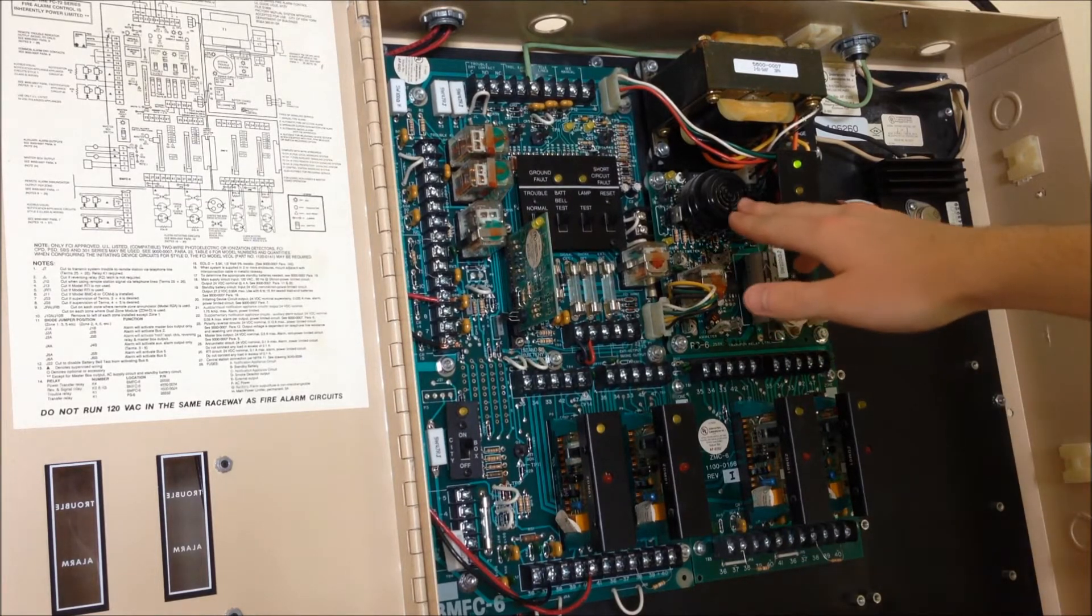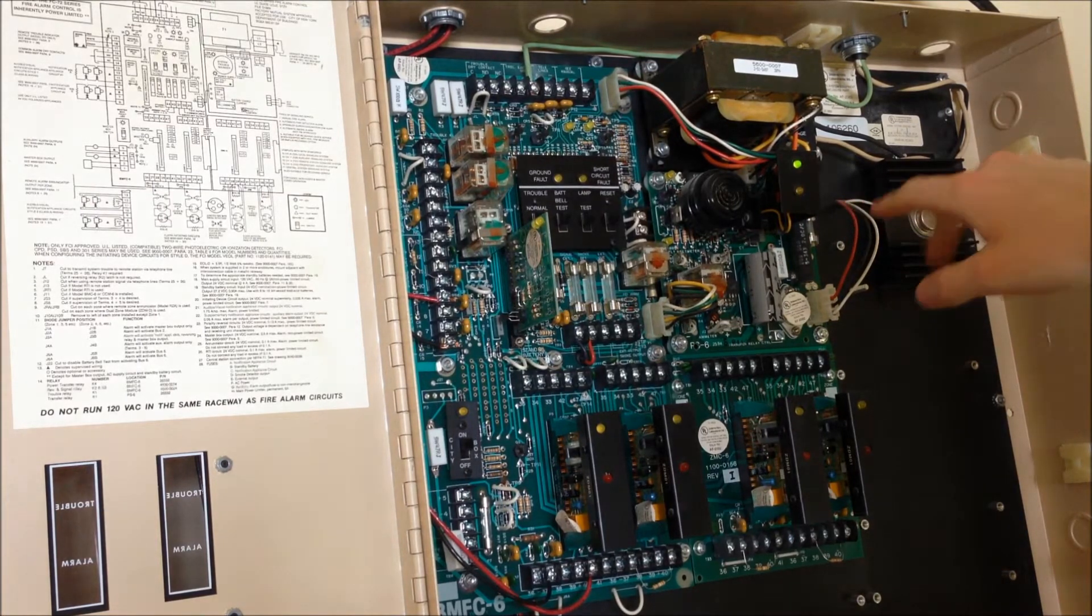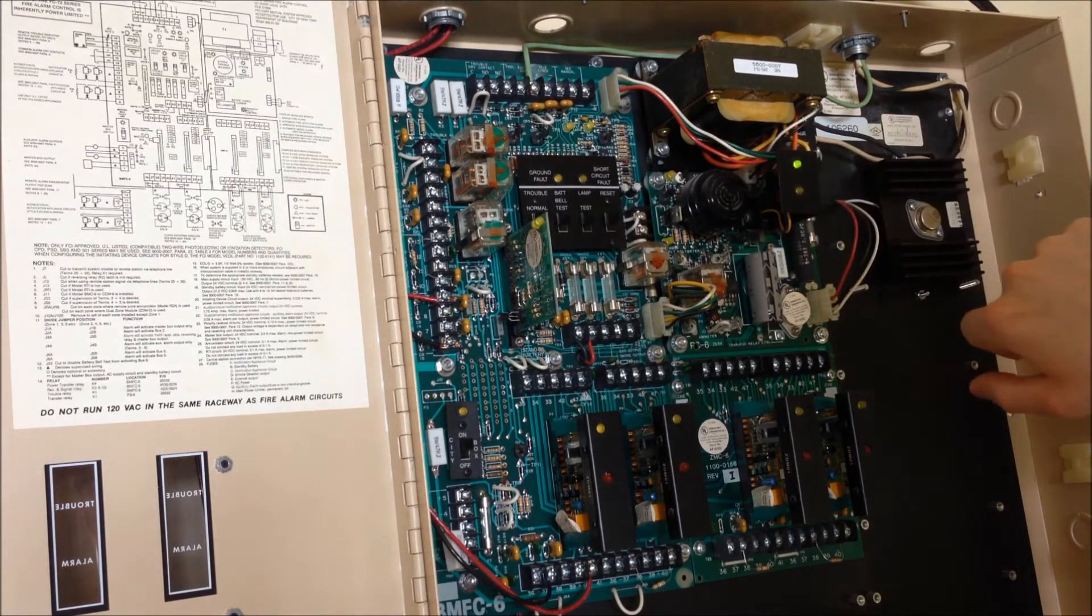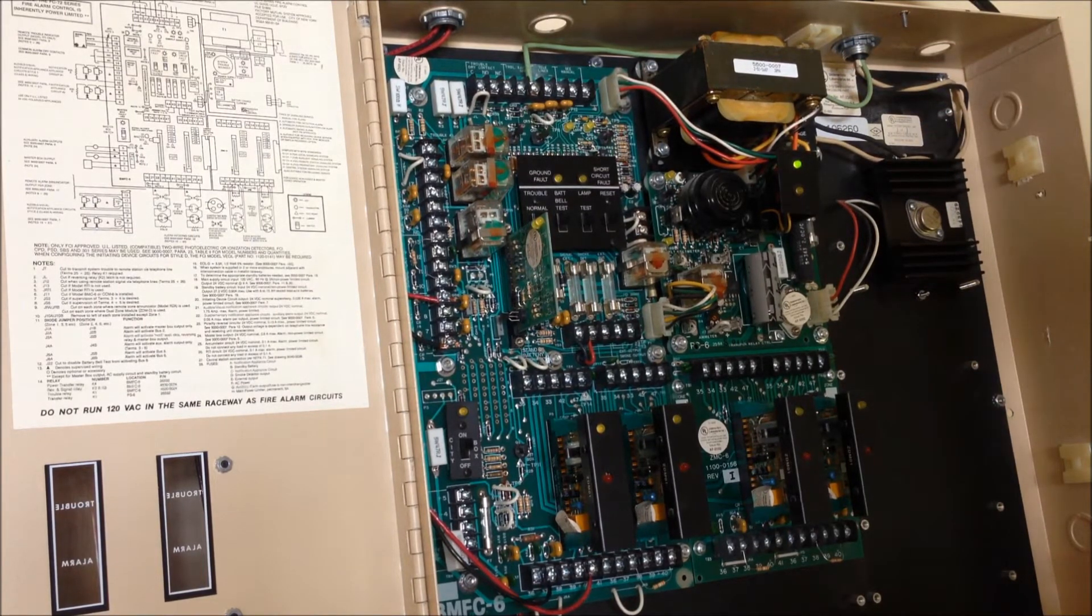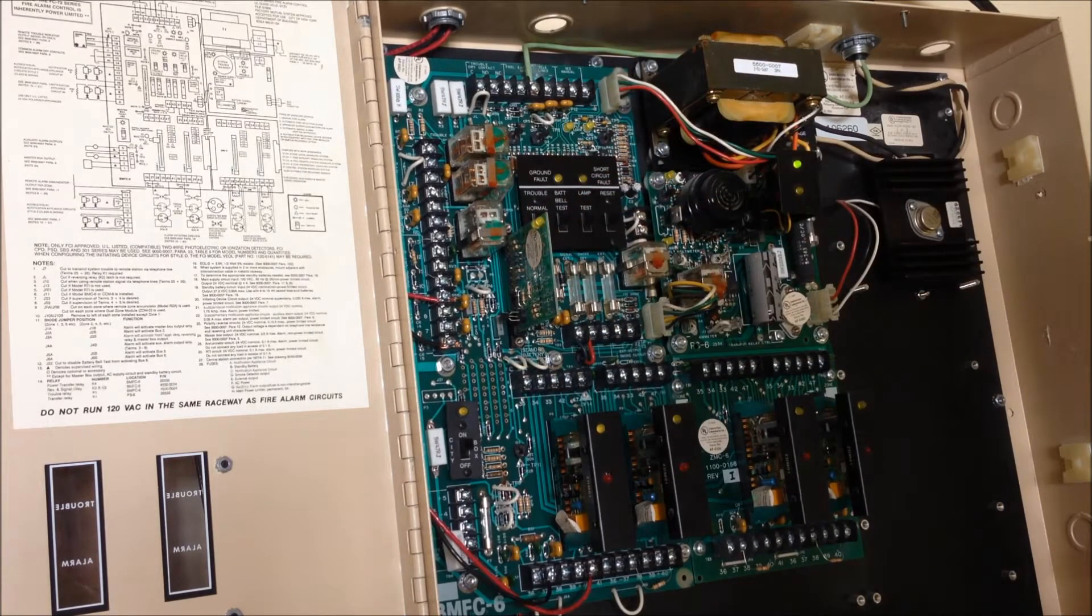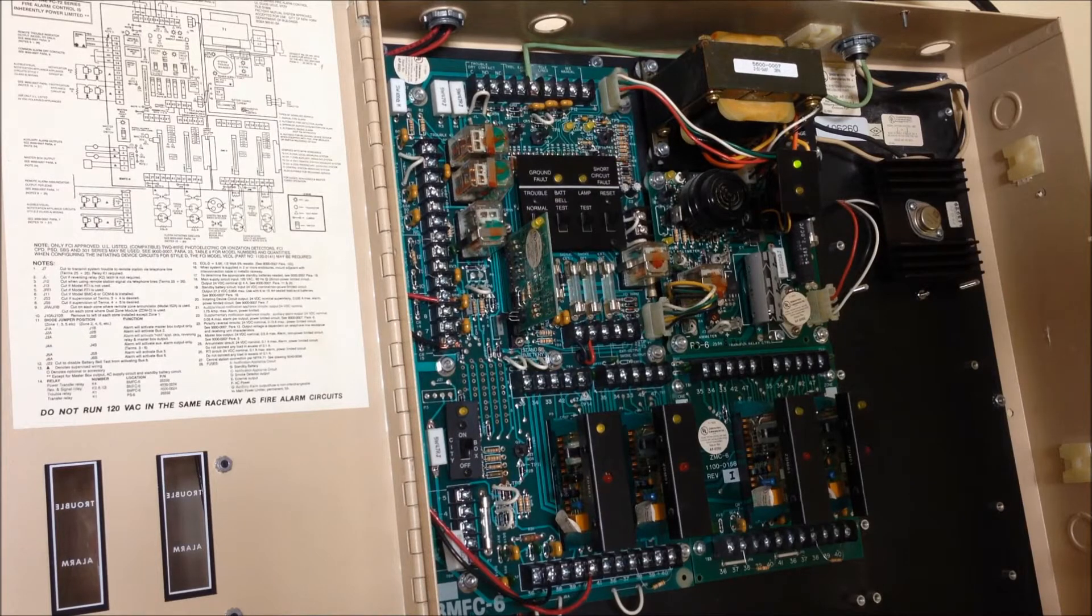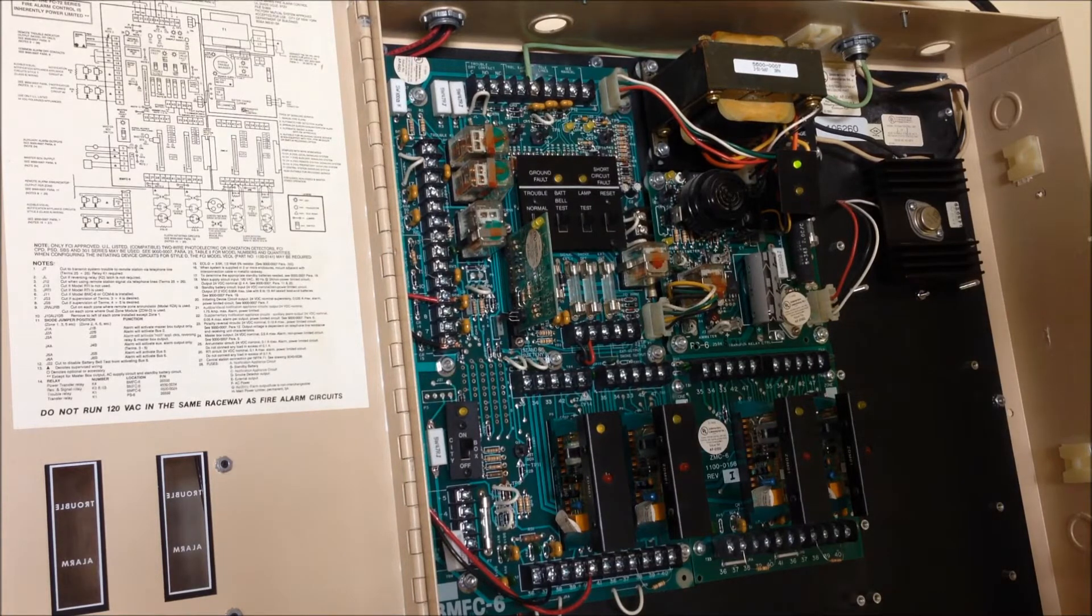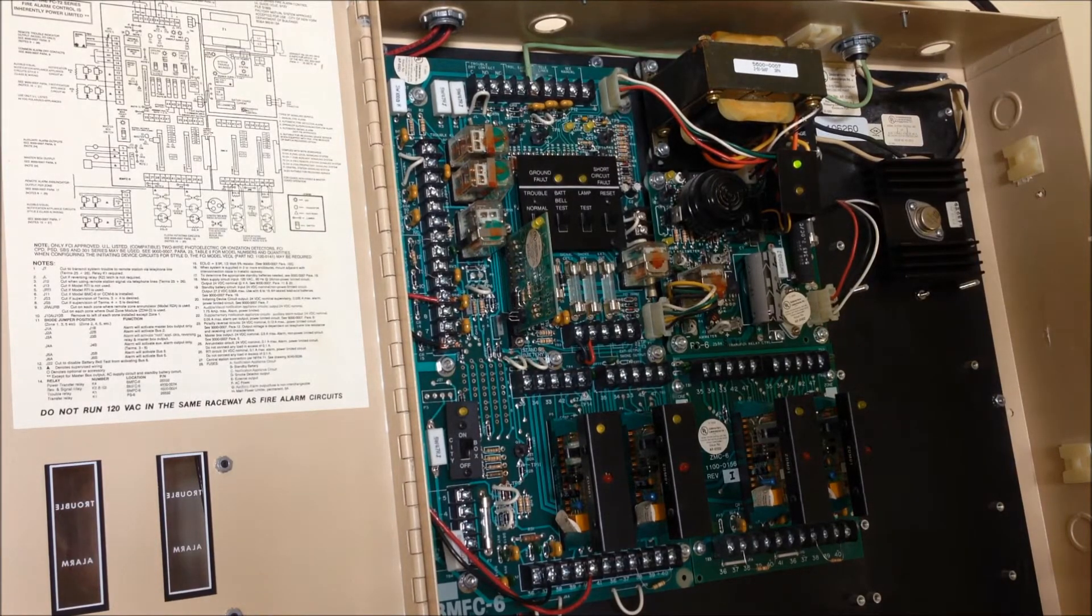We have the piezo up here, what you could call the main display even though there's really only two LEDs here. There's a battery low or battery missing LED hidden back there up on the upper left hand corner of the board and then of course up here we have all the power supply equipment. You can see over here on the left side of the frame we have the wiring diagram which is actually customized for the amount of zones that are in this panel, which I think was kind of an interesting move rather than just having a standardized diagram. They actually did put the exact zone cards and expansion cards that are installed in this panel.